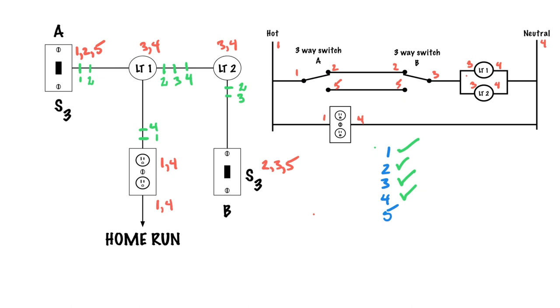Last number, five. I've got a five at three-way switch A and a five at three-way switch B. No other fives — no five at the lights or the receptacle. So I take my five through from switch A all the way through to switch B: five, five, and five. Check mark.